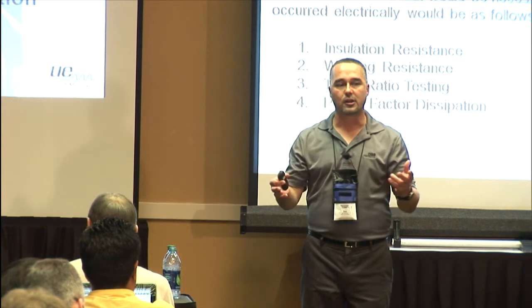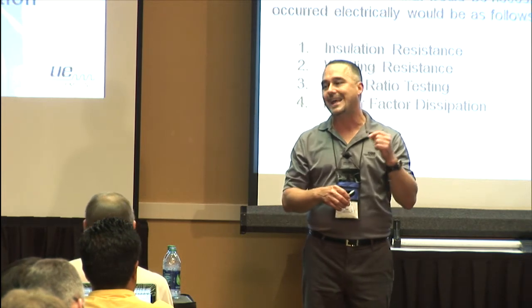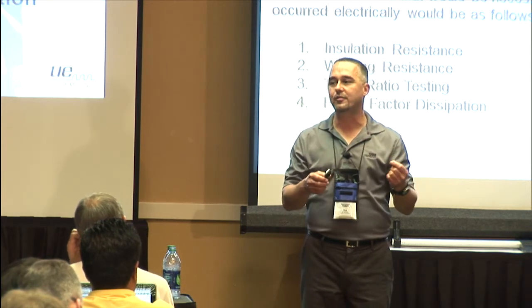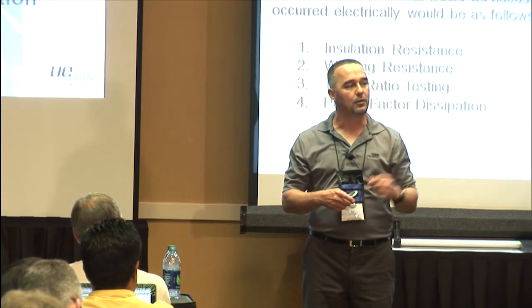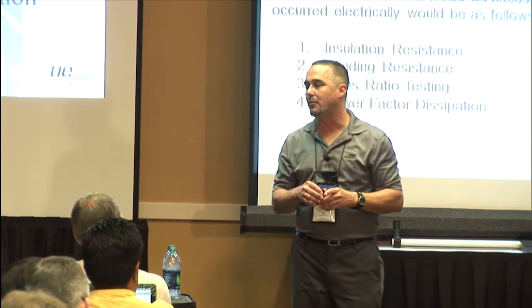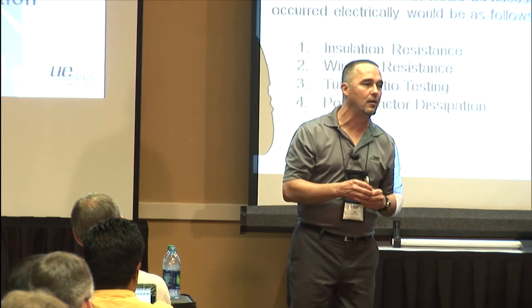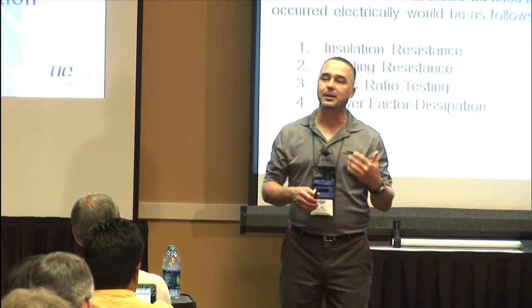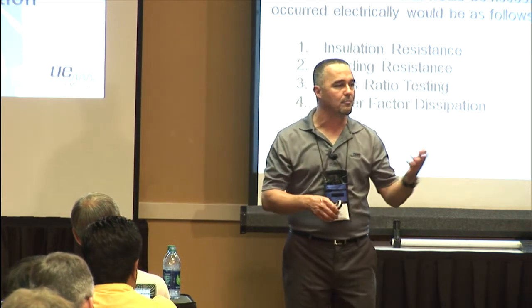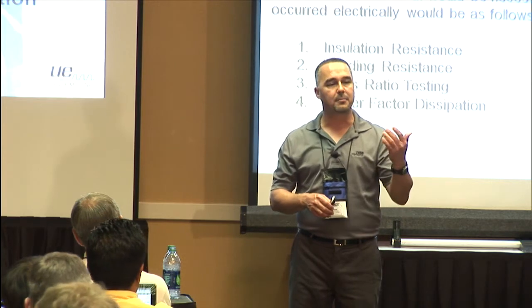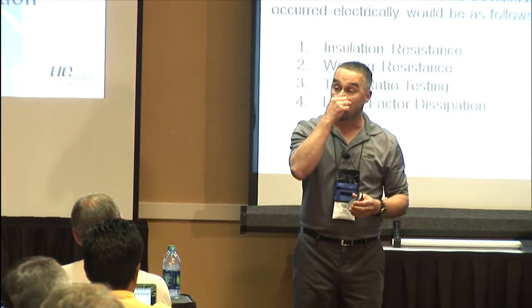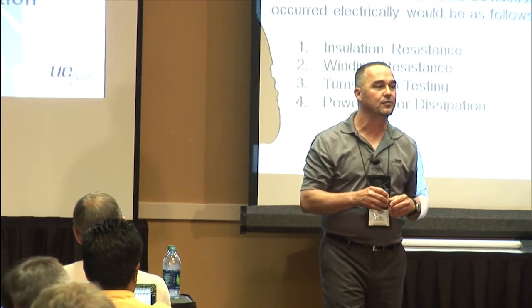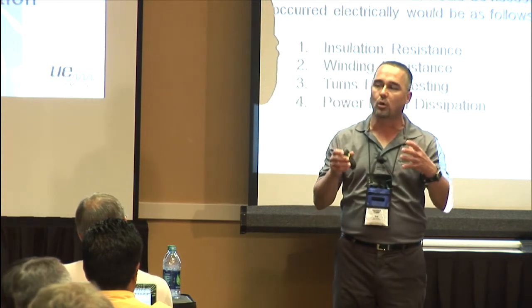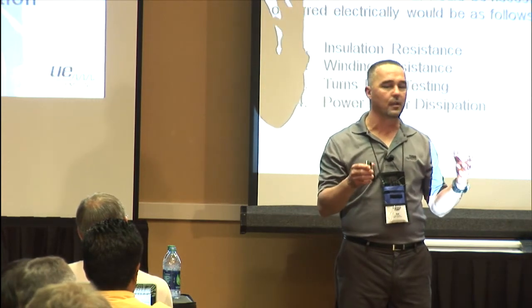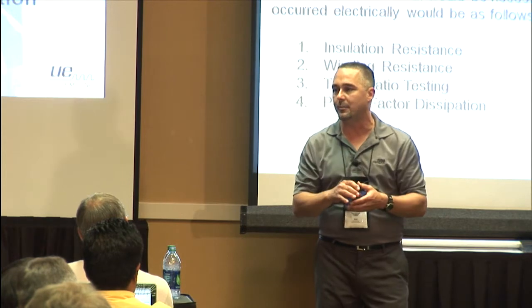secondary. A lot of transformers will have more than one tap on the primary side to allow you to apply different levels of voltage on the primary side and still maintain the same secondary voltage. That can be changed without ever messing with the taps, simply by getting turn-to-turn shorts. The other thing that can identify is problems within the core of the transformer related to the laminations and the bond of those laminates and things like that.